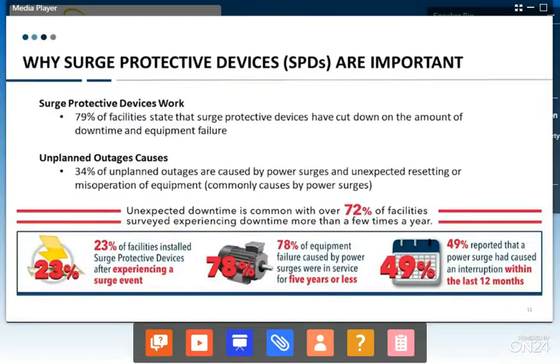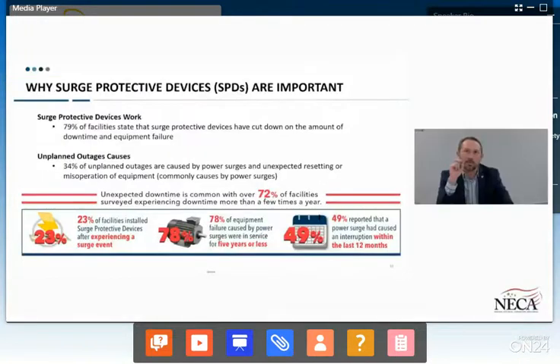Respondents from this survey have a good experience seeing that SPDs do have a positive impact on reducing that downtime. These are repetition of the previous infographics, but the key thing I want to call out is that 78% of surge misoperation failures were from equipment in service less than 5 years. So your newer equipment is causing the majority of your downtime, and again, it's not just the failures, it's also the misoperations.